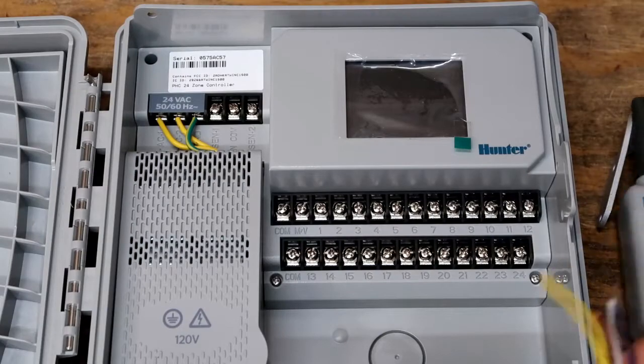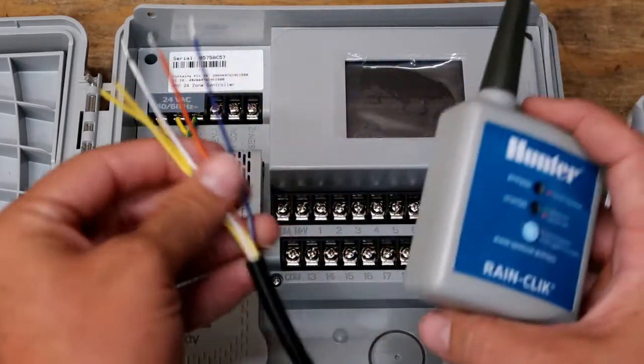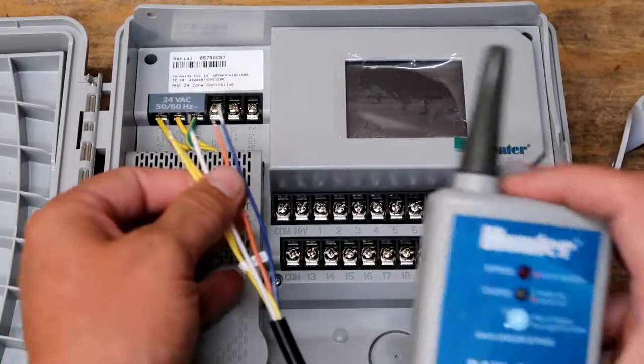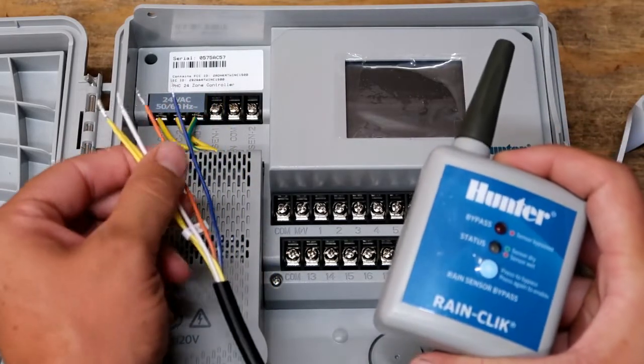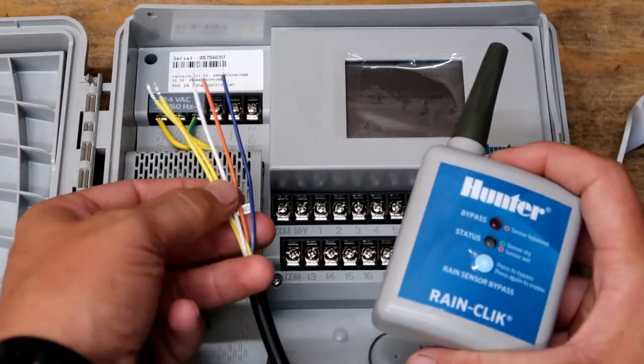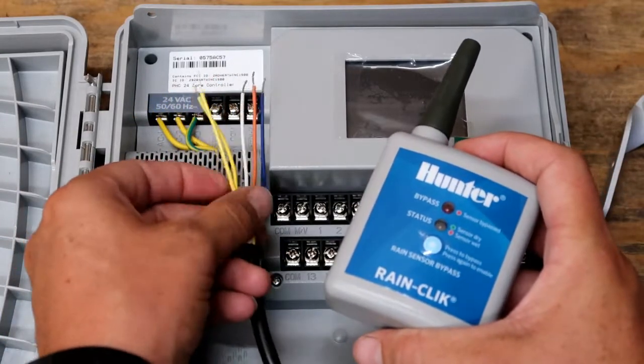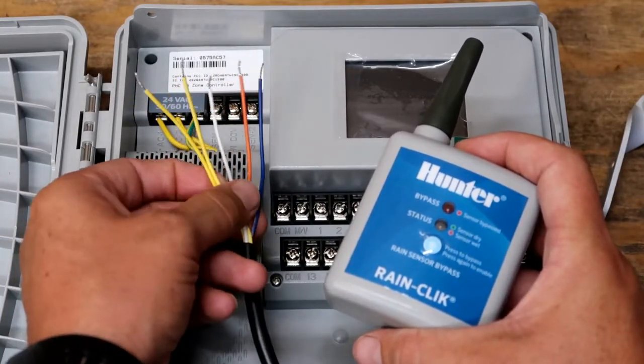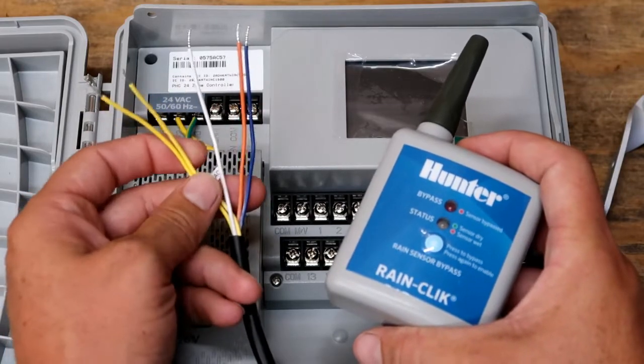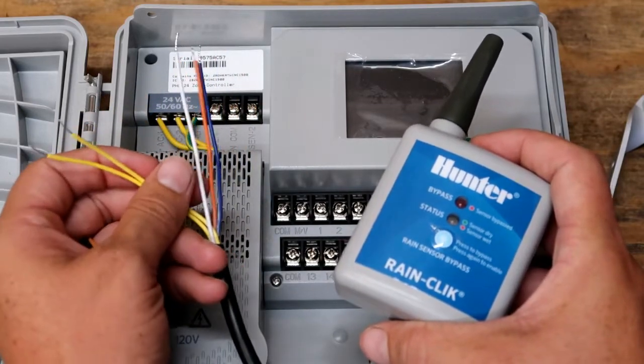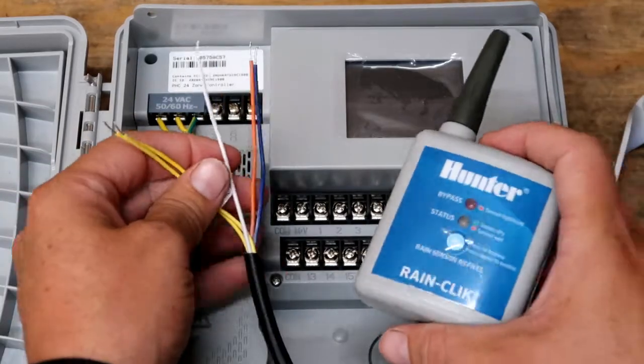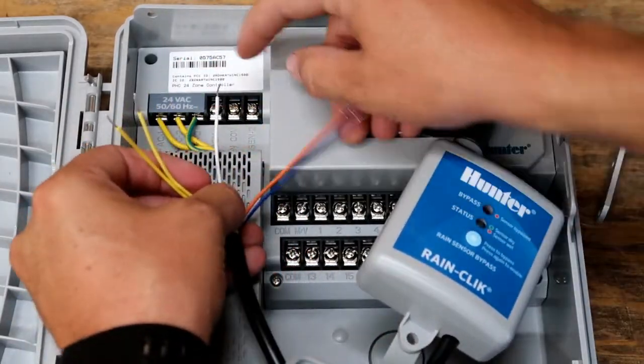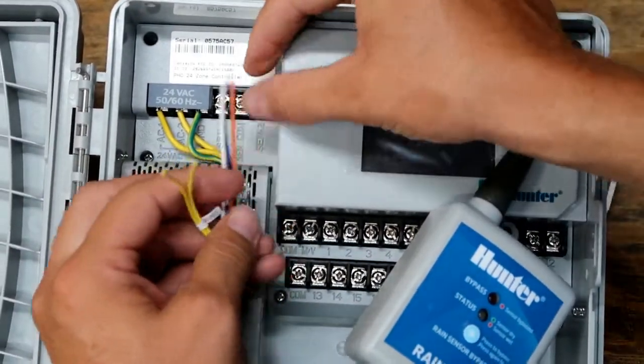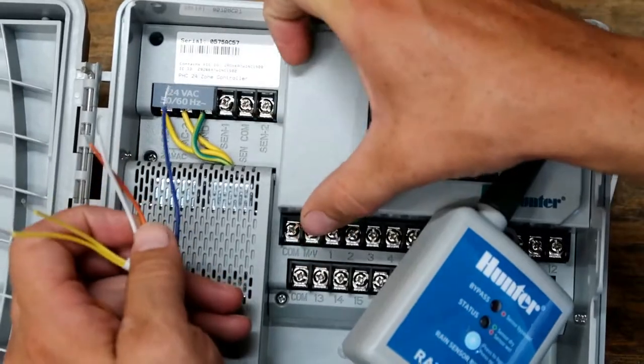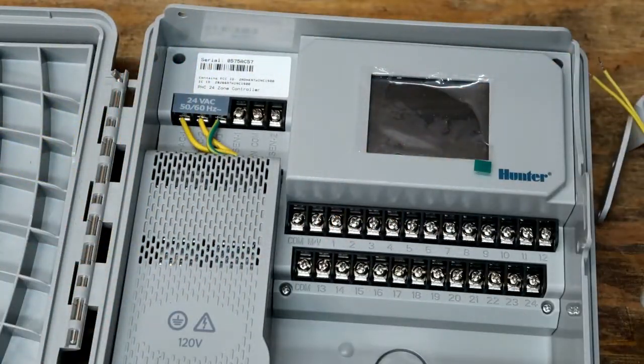So after looking up the information in the manual, it does not matter if you use a blue or orange wire. I'm sure you just have to program in here whether it's normally open or normally closed. And honestly, these controllers are probably smart enough now. You just say that it has a sensor, and it's going to look at the sensor and say, okay, 99% of the time it is open, and therefore whenever it's closed, we're going to shut off water, and vice versa. But you can use just the white wire there on the common. And then you can do the orange or blue on either sensor 1 or sensor 2, it shouldn't matter. And then you'll configure the rest in your settings.